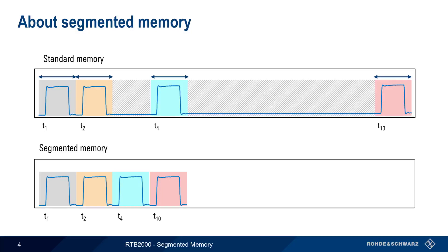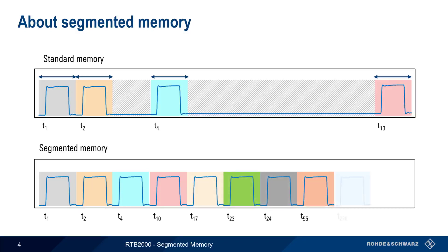The process of acquiring a certain number of samples per trigger and storing them continues until segmented memory is full. Note that the time between triggers can be quite long, making segmented memory very useful for catching rare events, analyzing slow-speed serial protocols, etc.